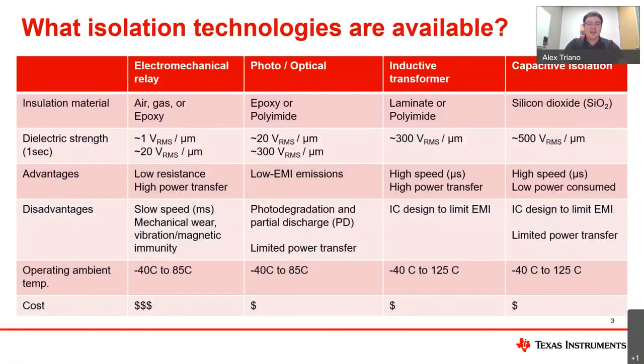Now, let's take a look at some of the isolation technologies that are available for these switches. On the left, you'll see electromechanical relays. These devices often use air or a specific mixture of gas as their dielectric material. The strength may be in the range of 1 to 20 volts RMS per micron, which means as a result, these solutions need to be physically large in order to achieve sufficient isolation for high voltage. The benefit of these relays is primarily the low on resistance achieved, since they essentially create a metal-on-metal connection.